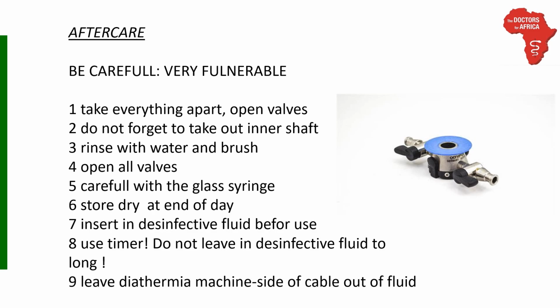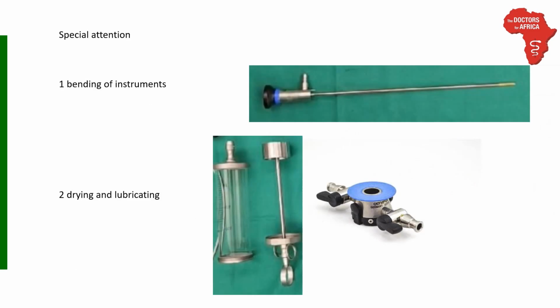Read the instruction for the sterilization fluid and adhere to the minimum and the maximum time you put the instruments into this fluid. The instruments might either be not sterile enough or they will get damaged by the aggressive fluid. Leave the part of the cable that goes into the diathermia machine out of the sterilization fluid. All instruments are made of metal, but it's all thin-walled. If it bends, the parts will no longer fit. If the ocular or telescope bends, you cannot see through it anymore.